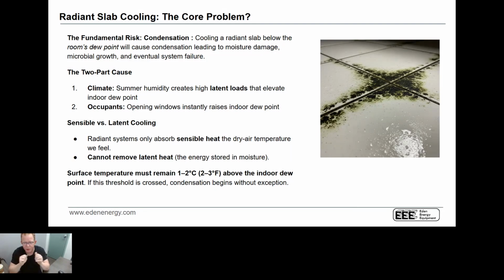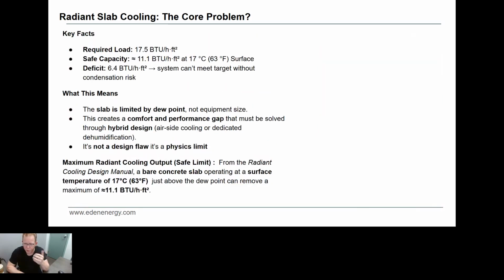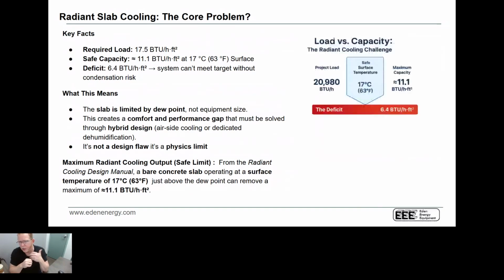Really, the key things we need to keep in mind is, one, we want to keep the surface temperature above the indoor dew point temperature. And we also want to make sure that we are always in a scenario where condensation is not going to happen. So that is through proper controls, and it's also through proper mitigation. So if we look at the scenario we had, I put a load out of 20,980 BTUs. That puts our required load at roughly 17.5 BTUs per hour per square foot.